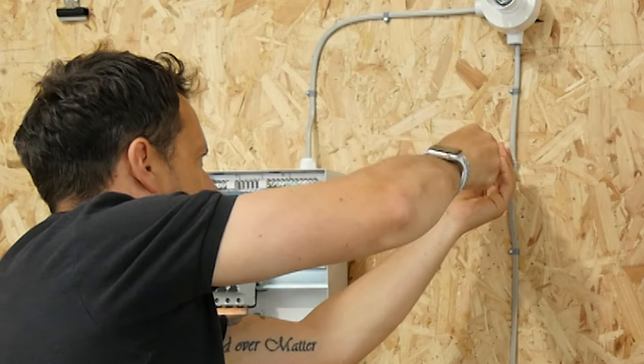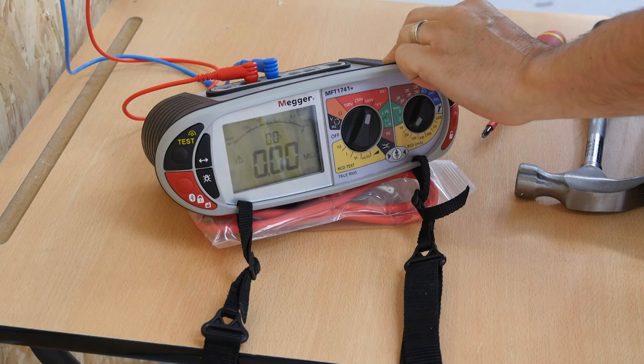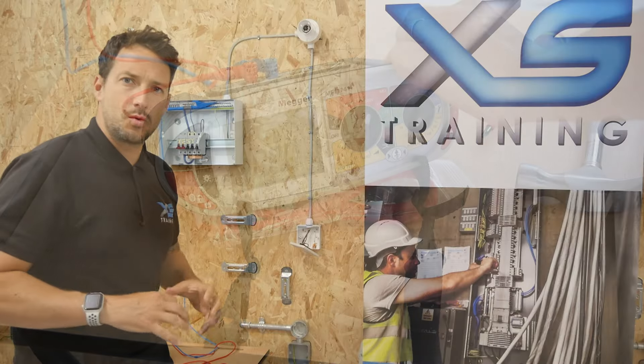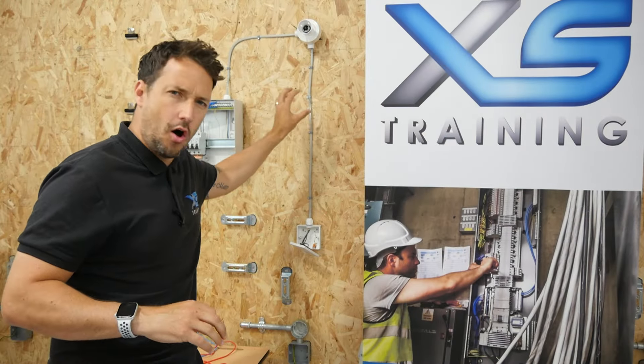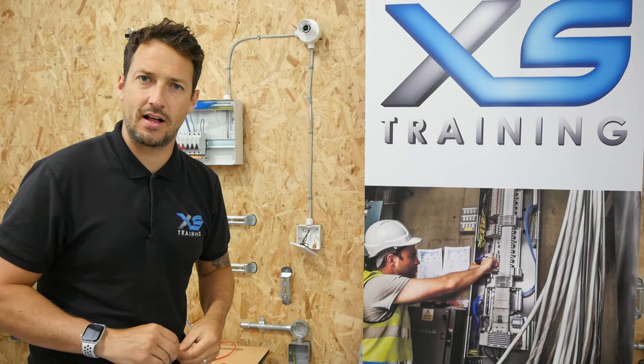Let's cause some damage using a screw. And there we have it — the first time we've got the reading of a short circuit. So in the end, we've had to cause a lot of damage to that cable to get those insulation resistance values down.